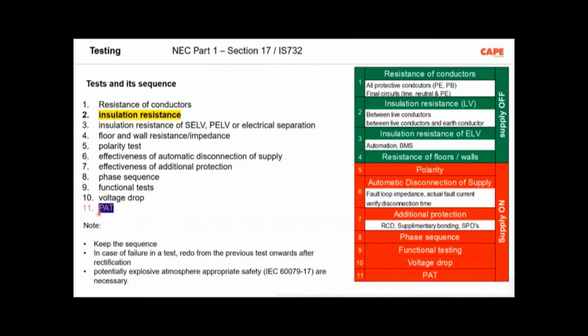In Europe and other countries, they started doing test number 11, which is called PAT, portable appliance test. Before you put the portable appliance into your good electrical system, you are supposed to do this test, and you connect only good portable appliances into your system. As a result, you are able to achieve safety in a whole way. So basically, if the equipment standards are followed and if the equipment are tested as per the Indian standards, the equipment is unable to create a fire. The chance of fire from the equipment is absolutely less because these tests are mandatory.